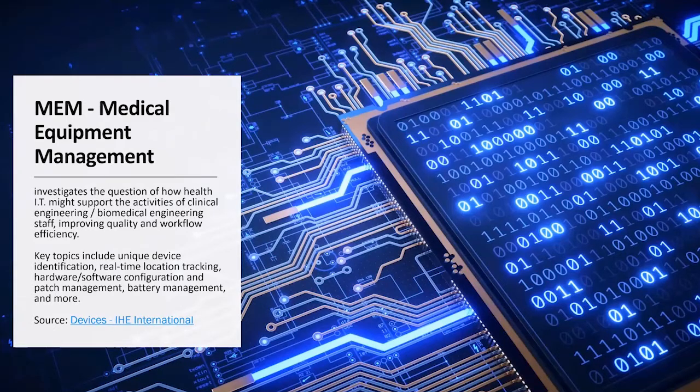The medical equipment management, as Ted mentioned, is the core piece here. This is where we actually get to leverage that IT information to benefit clinical engineering directly, whether we're assisting with workflows or quality. Things we'd be getting would be unique device identification, battery management, RTLS, and even configuration data.